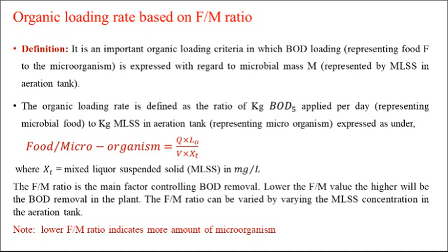XT is the mixed liquor suspended solids in milligrams per liter. This F/M ratio is the main factor controlling the BOD removal. The lower the F/M ratio, the higher the BOD removal rate in the aeration tank. The F/M ratio can be controlled or varied by varying the MLSS concentration in the aeration tank.